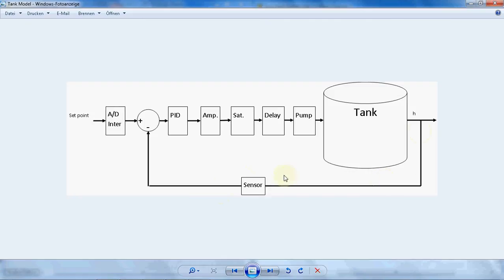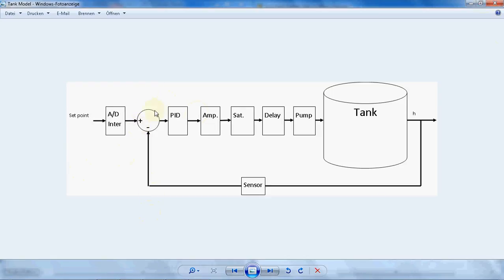First of all we need a sensor to measure the level of water in our tank. The sensor passes a voltage to the summation point, and the minus of the measured level of water will be summed with the set point, which is passed through an analog-digital interface. They will be summed here and an error is produced, which goes to a PID controller.